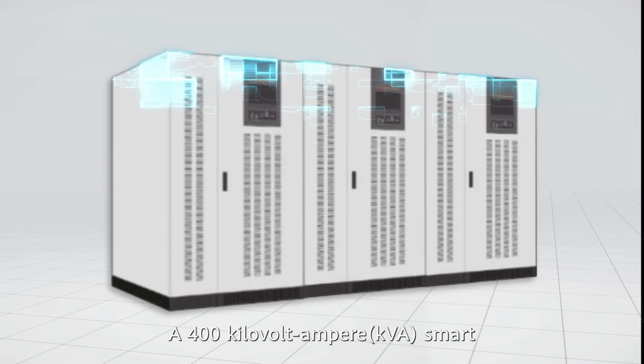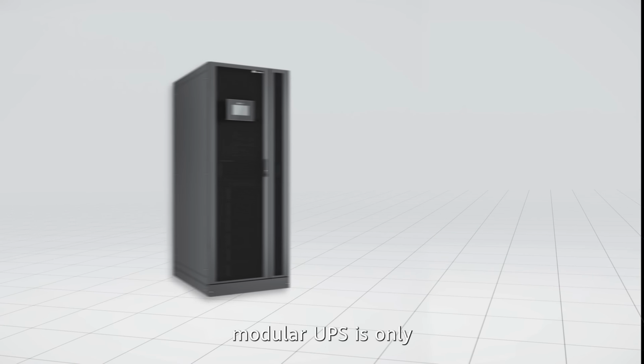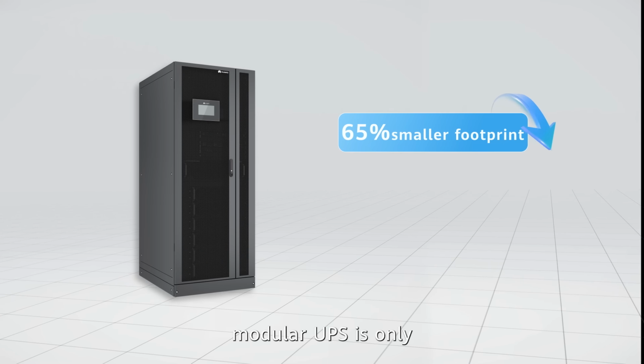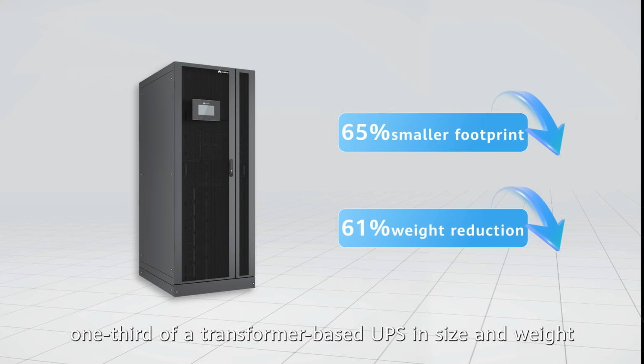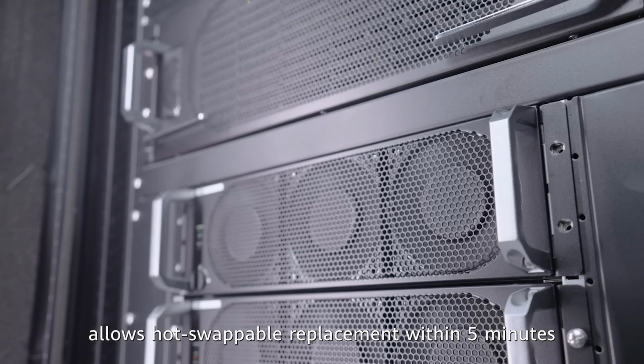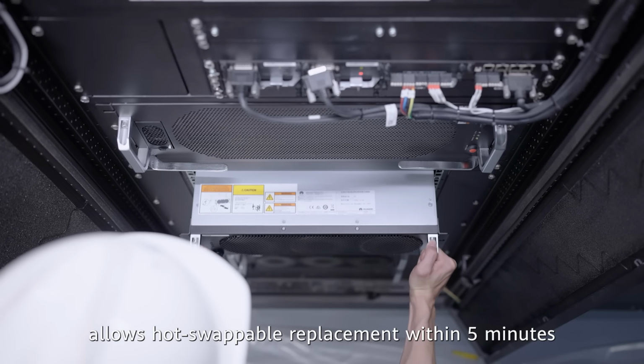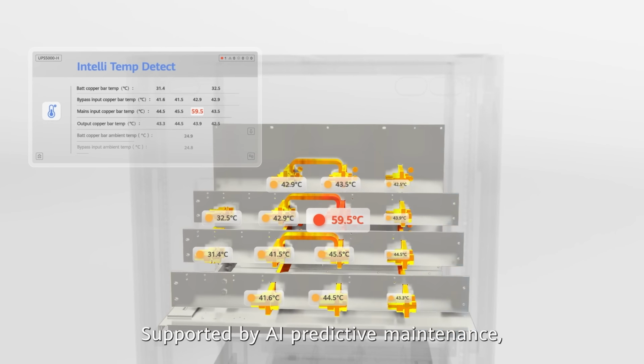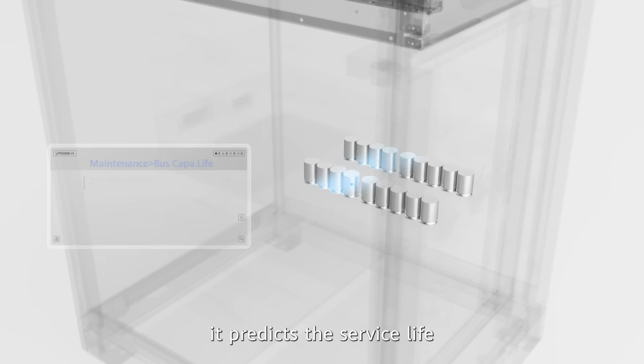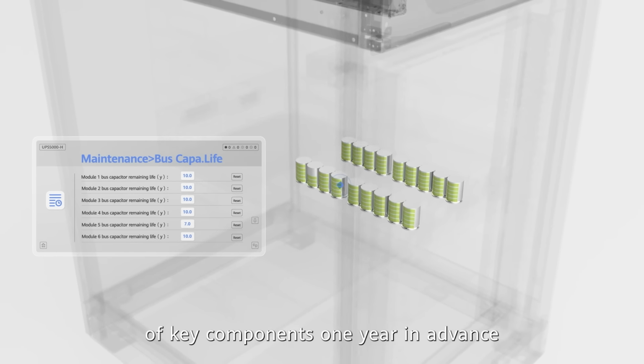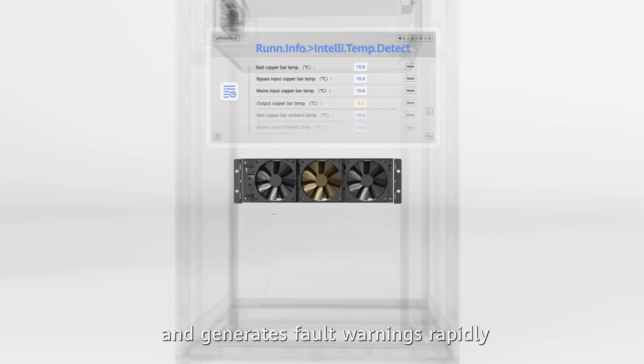A 400 kVA smart modular uninterruptible power supply is only one-third of a transformer-based uninterruptible power supply in size and weight. The modular design allows hot swappable replacement within 5 minutes.